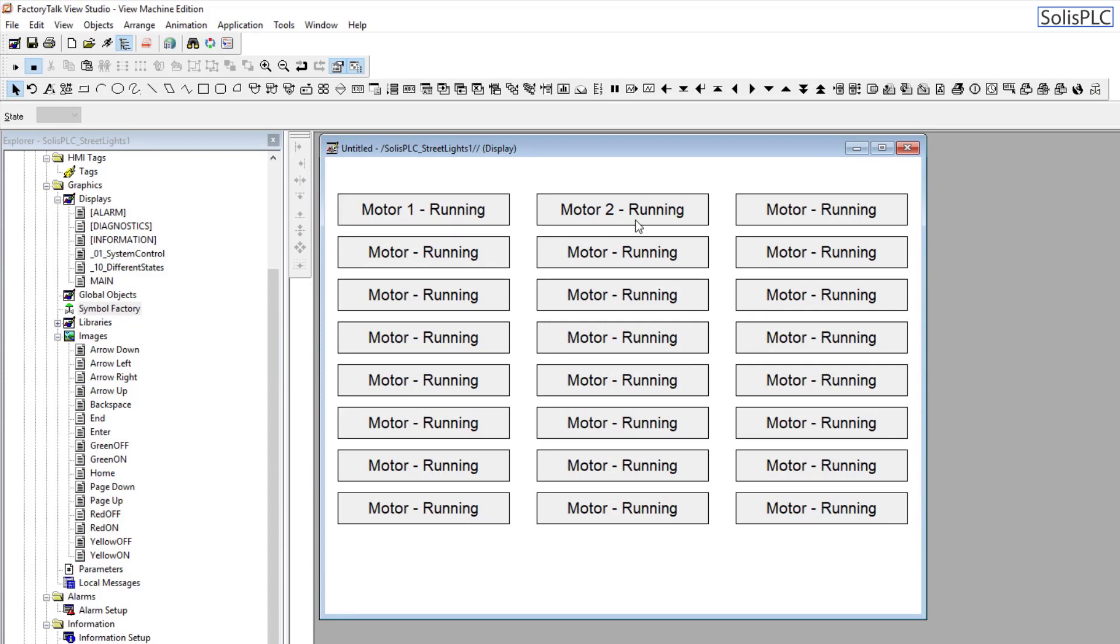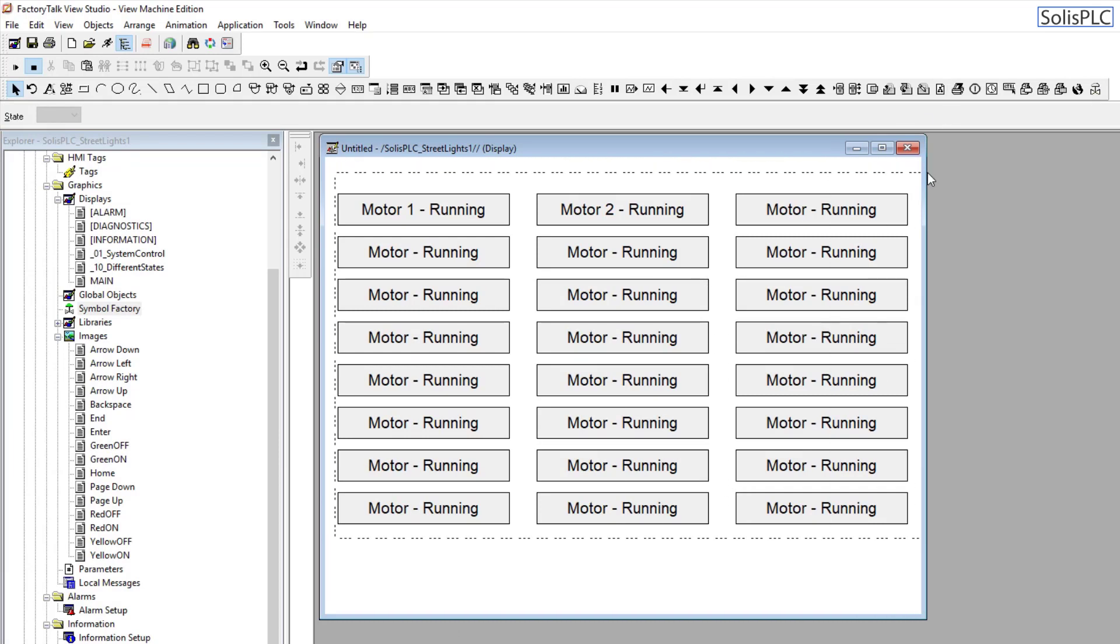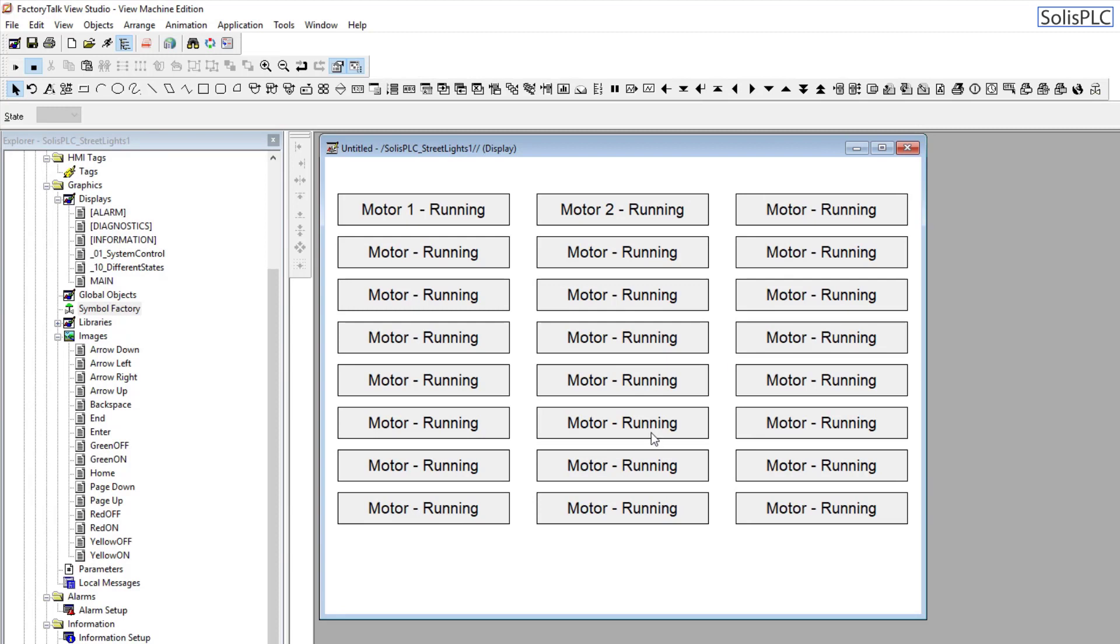That being said, you can have a display which has multiple axis, buttons or status bits or what have you, but it's going to be looking a lot nicer. So here, for example, I wouldn't necessarily leave this as is. I would probably include a title bar on top of the screen. So there's going to be some pixels reserved for that. And I'm going to include for this pop-up, some kind of a cancel button or a navigation at the bottom. So it looks really neat. Spend your time realigning your objects.